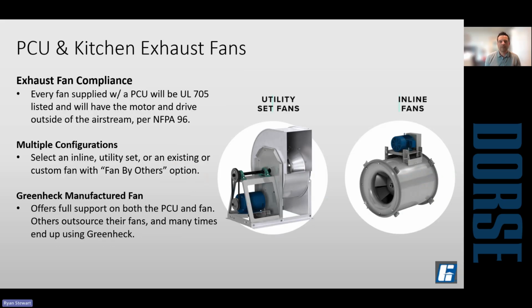Various configurations of fans. This would be an application where you may still see some belt drive fans because they're going to be high CFM and traditionally high static pressure. Most common, I would say, utility sets. They're most configurable, but in some cases, the inline fan is a good fit for it as well.